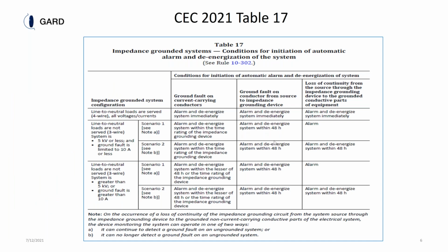So CEC 2021, Table 17 looks at 3 distinct items for inclusion of what to monitor. One is a ground fault current in current carrying conductors. Second, it is an open or short circuit in the conductor leading from the X0 bushing of the transformer or power source to the resistor. And the third thing is an open circuit.